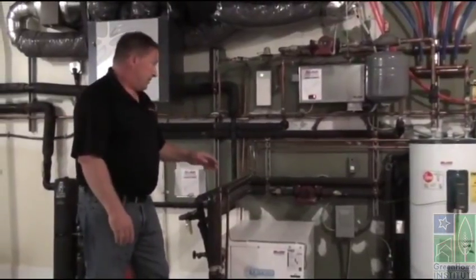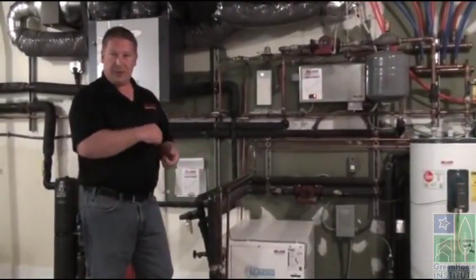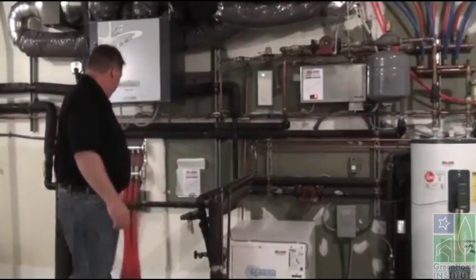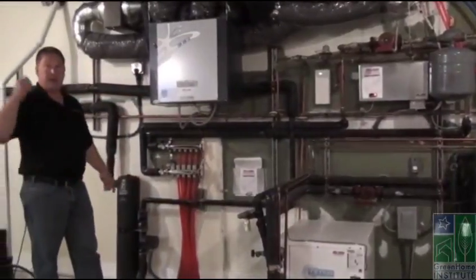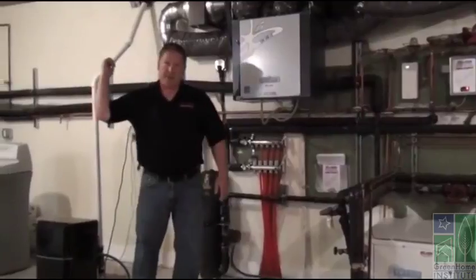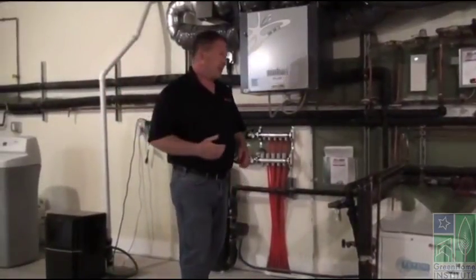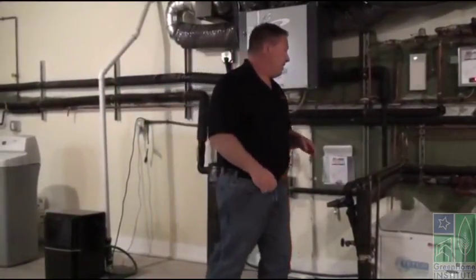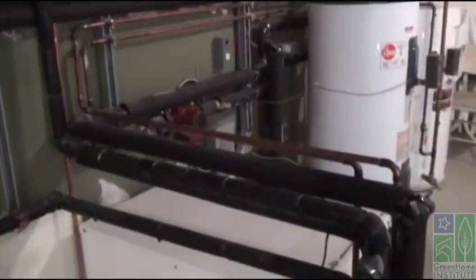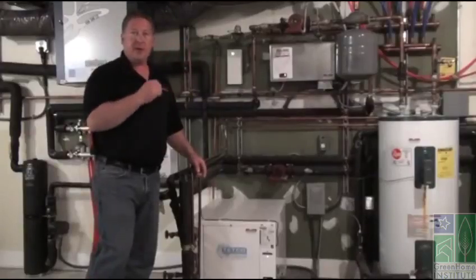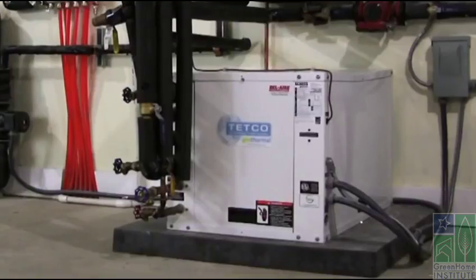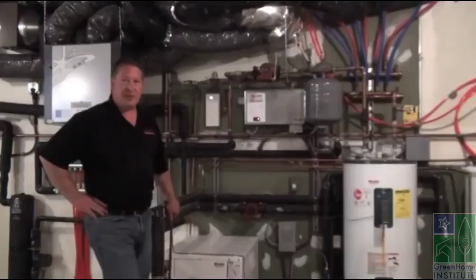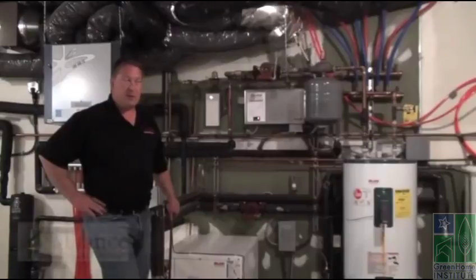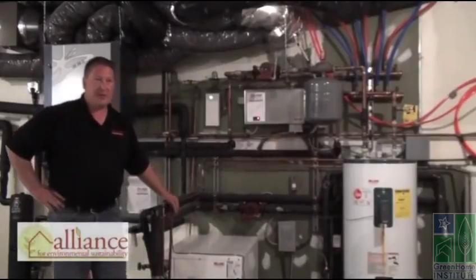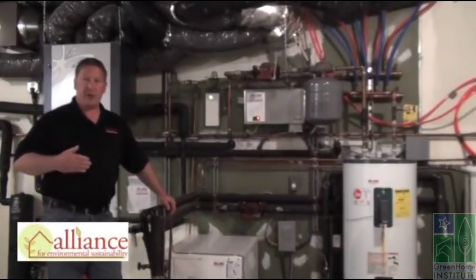There's some pumps in there. There's sealed bearing pumps that circulate the water through the system. There's one here that circulates water outside into the earth to pick up or deliver heat to the earth outside, and then there's pumps here that pump that water into whichever zone is calling for heating at the time. And this system is somewhat unique. There aren't a lot of them installed, but it does cooling as well. Again, as I mentioned, this is not a forced air system, so there's no air movement.